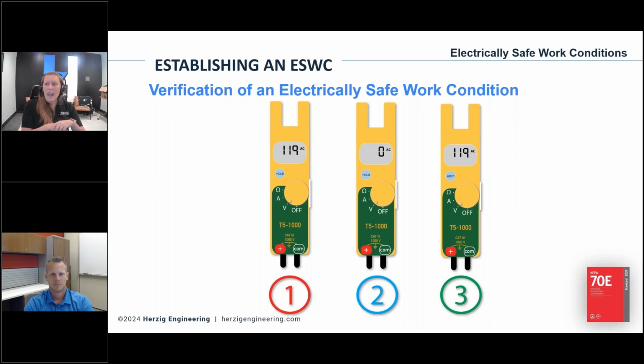So he calls up a friend and says, hey, can you come here and bring your meter? Borrows it, goes through the same process, checks phase to phase, phase to ground, and it turns out one of the phases was still energized. And for some reason, he thinks that whenever he was testing that phase, maybe there was a transient, maybe there was a spike in the current, we don't really know. It damaged his meter, it malfunctioned, got stuck at 0. And if he had trusted that 0 was 0 without verifying the meter worked, he very well could have taken his PPE off, stuck his hands in, and maybe gotten shocked or worse. Okay, so this is life-saving stuff. Yeah, that second live is important. We're putting our lives in the hands of an electronic device. Yep. Let's make sure it works, okay?